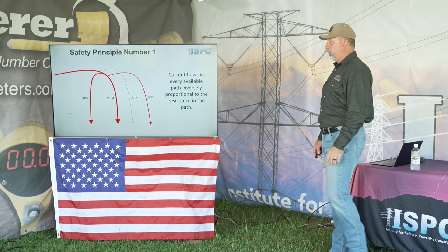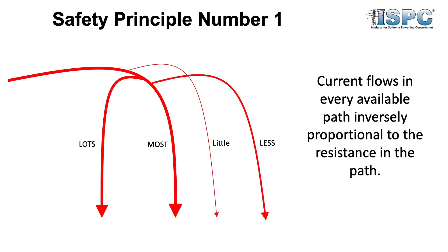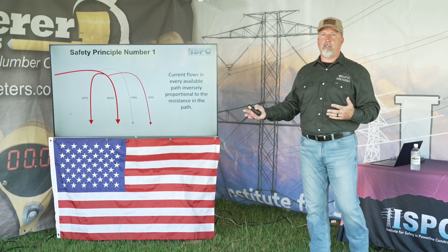Safety principle number 1: current flows in every available path, inversely proportional to the resistance in that path. If you, as the worker, are one of those paths, you're going to see current. Should there be an induced voltage, a fault, or a switching error, one of these current paths — lots, most, little, or less — is going to be you if you don't have yourself properly bonded and grounded into your work zone.